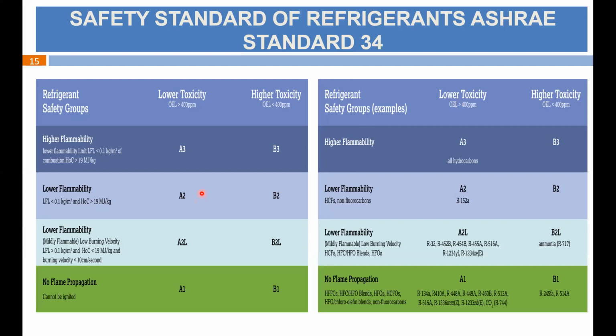So intermediate refrigerants A2 and B2: A2 is lower flammable with lower toxicity, and B2 is higher toxicity, low flammable. There is another refrigerant class, A2L and B2L. This is mildly flammable. Mildly flammable is the category in which some very prominent refrigerants like R32 fall. Under some conditions, at some burning velocity, the flammability happens. So these are all A2L and B2L, lower flammable or mildly flammable refrigerant classes.